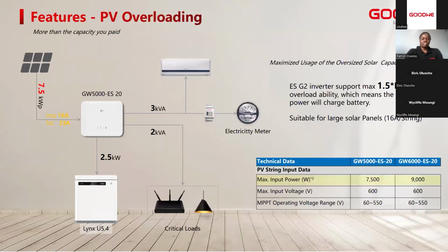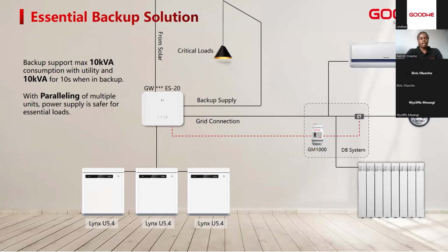One more thing to note is that the ESG2 backup solution gives you an option of expanding your battery storage. With the ESG2, the minimum you do is a single Lynx U5.4 battery, but then you can increase your battery storage in parallel up to 6 pieces of the Lynx U5.4. A single piece is 5.4 kilowatt hour. Now, if you expand up to 6 pieces, you have the capability of installing up to 32.4 kilowatt hour of Lynx U5.4 battery.